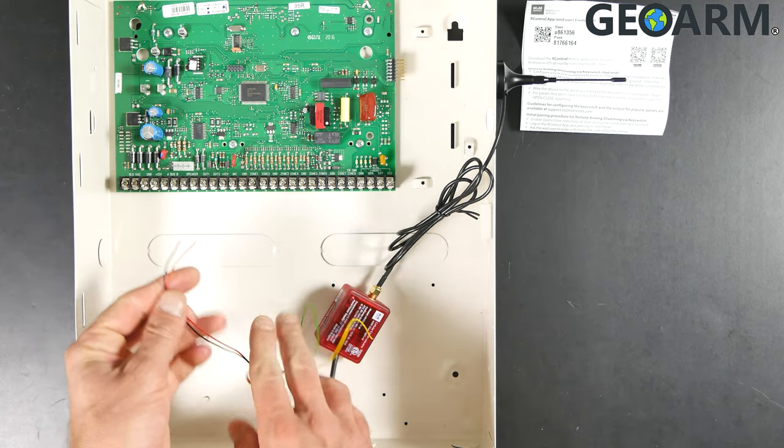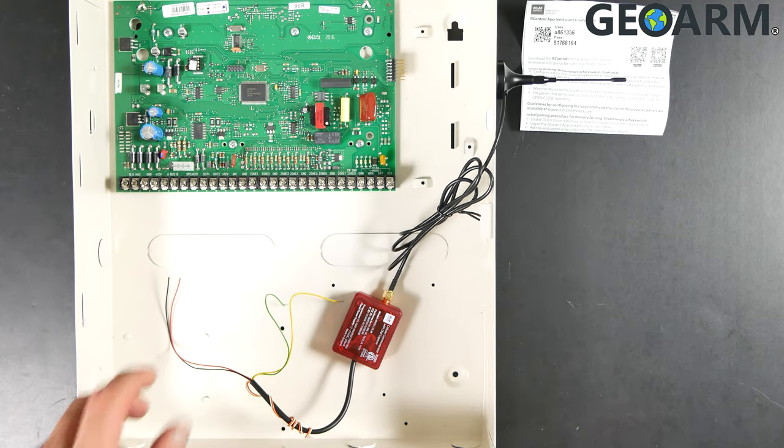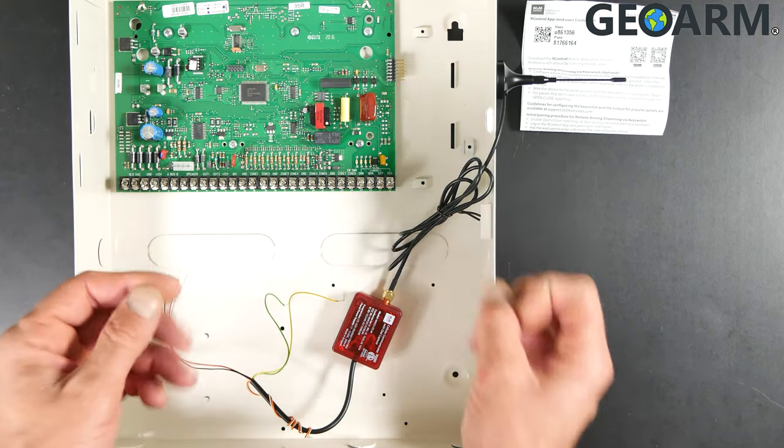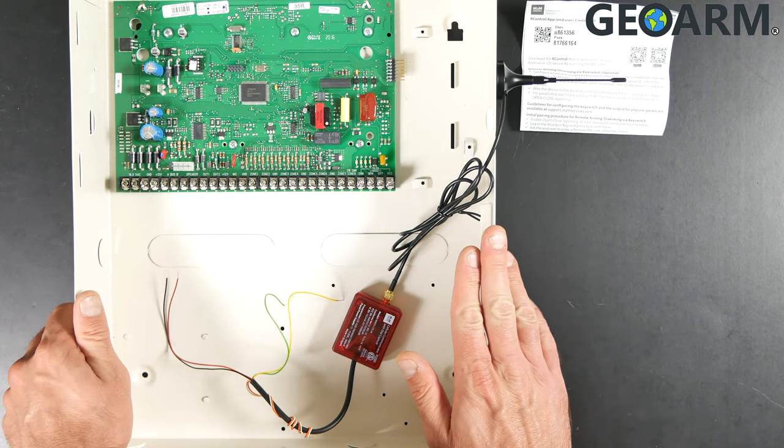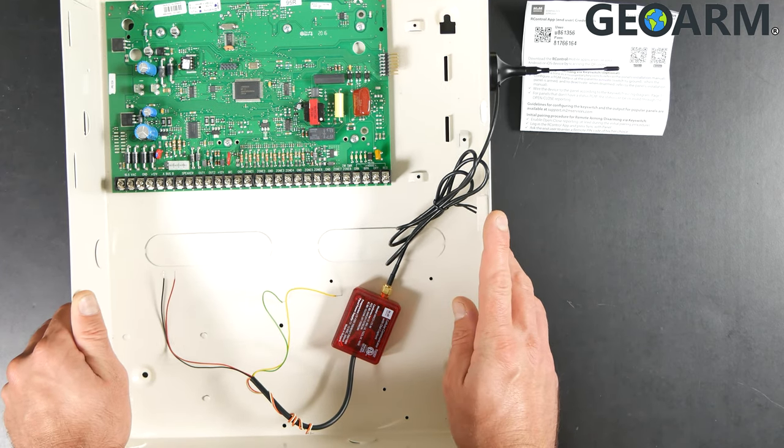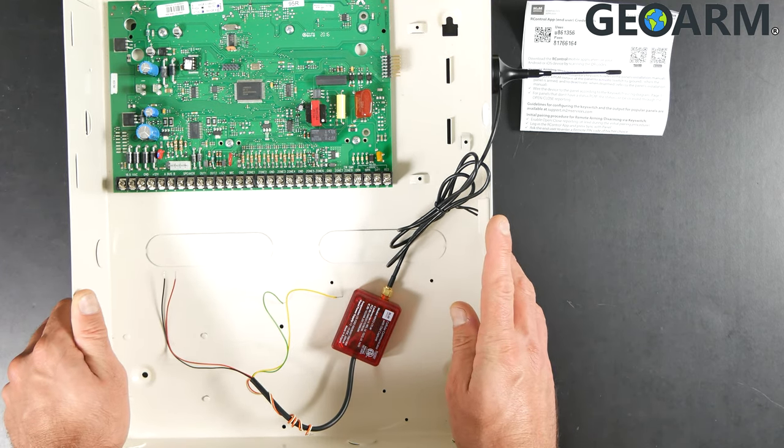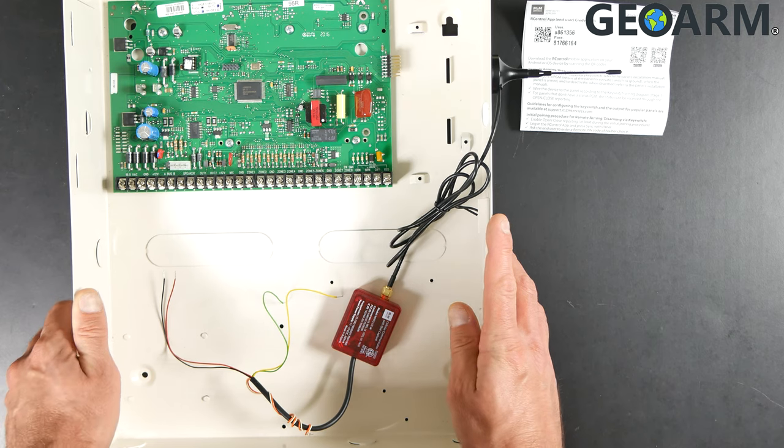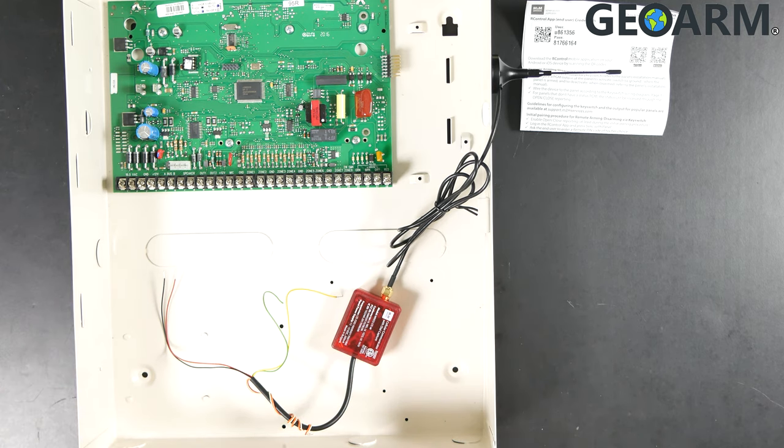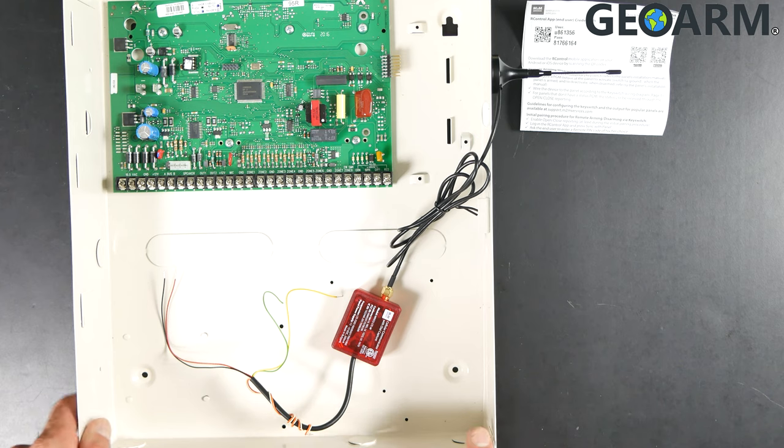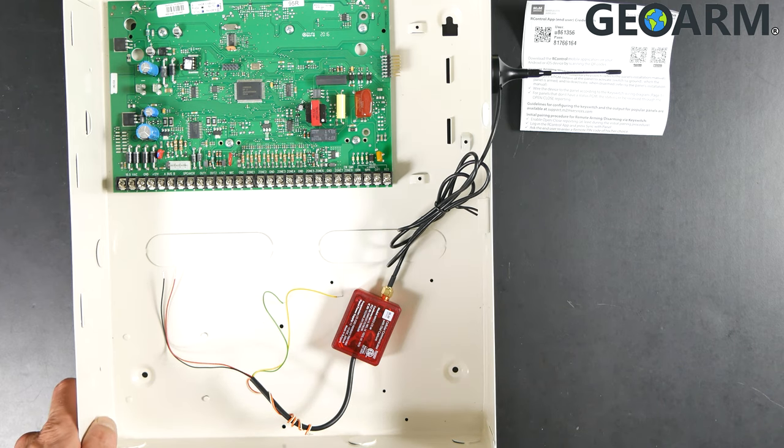We'll go ahead and get the red and black wire in first. Now, prior to doing this, you need to make sure that your GE Concord 4 panel is completely powered down. You're going to unplug the backup battery and also unplug the power supply. Once you do that, confirm that it's completely powered down by checking your keypads and verifying that the keypads are also dead.